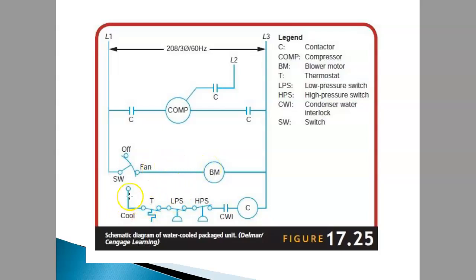and it has this is switch, it has thermostat, low pressure switch, high pressure switch, condenser water interlock, and the last one is what? Relay for the contactor. Okay, how does it function, this circuit? So for example, here we have the switch in off and fan, so it means the fan, this is line of fan, this blower motor will operate, although the compressor is not operating, but the blower is operating. Okay, I mean the fan is moving.